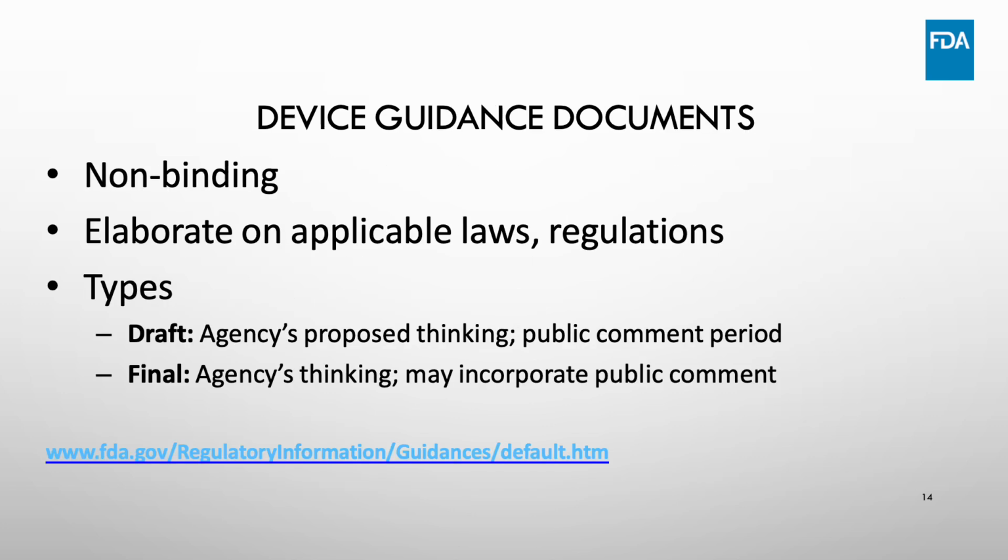Sometimes, the FDA laws and regulations are not sufficiently detailed to describe how FDA intends to regulate a device policy. In such cases, FDA will publish a guidance document that describes what FDA is thinking. A guidance document is not binding, but it does reflect FDA's current thinking, so it can often be an excellent resource of detailed information and clarifications on a particular policy.